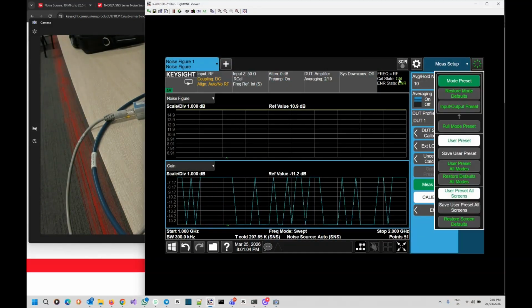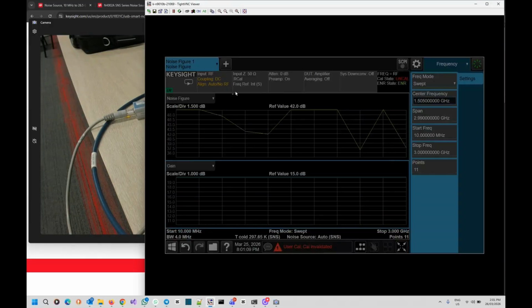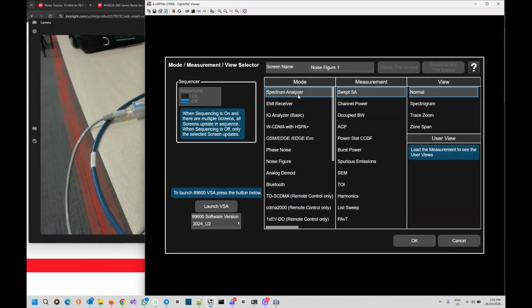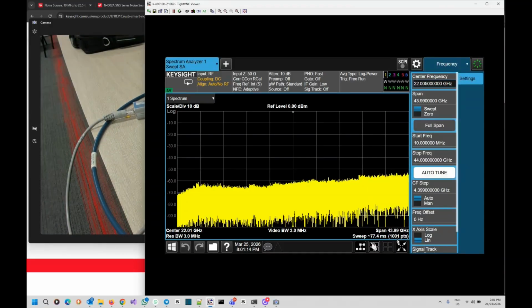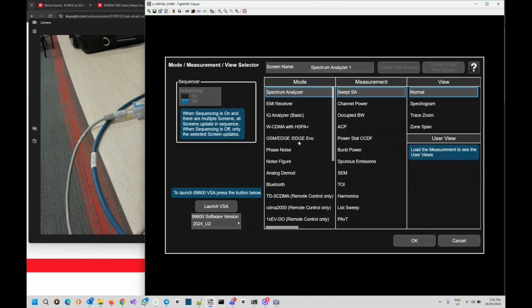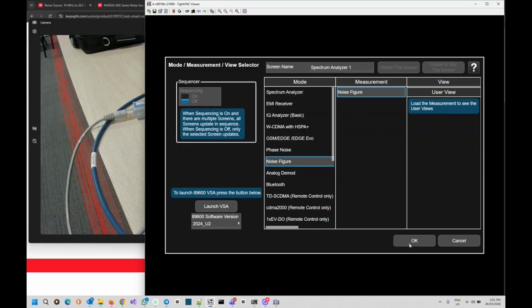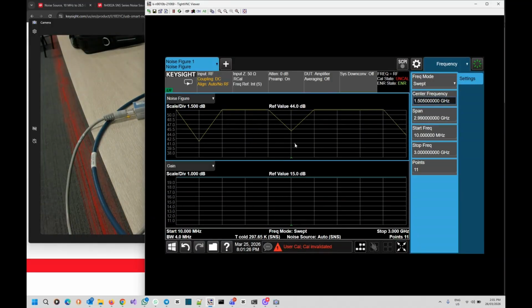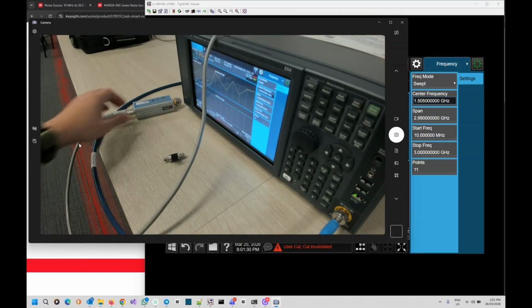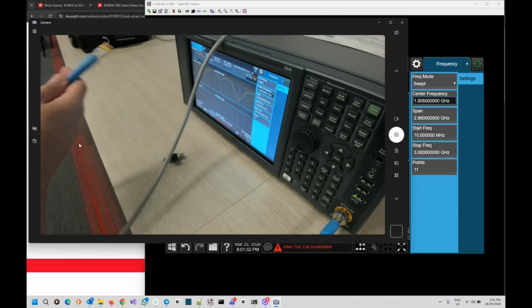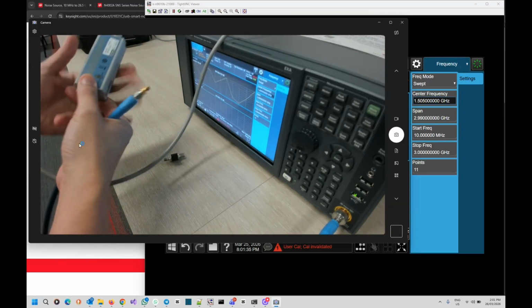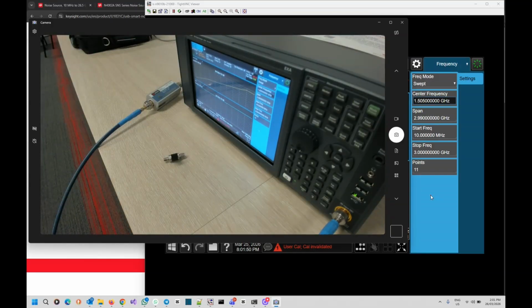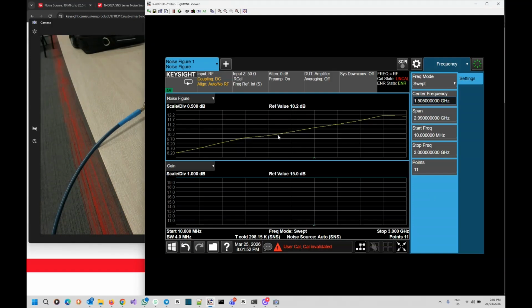Let's preset everything. By default, if you turn on a spectrum analyzer, the first screen you see is the spectrum analysis. Go to Mode and look for Noise Figure. I haven't set anything yet. The first thing I want to do is connect the cable from the spectrum analyzer directly to the noise source. We expect to see a flat line here, but it's not because we haven't calibrated the system yet.